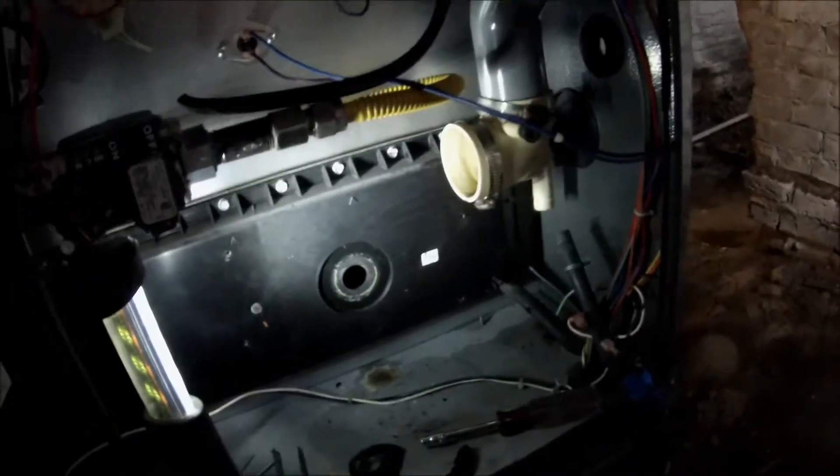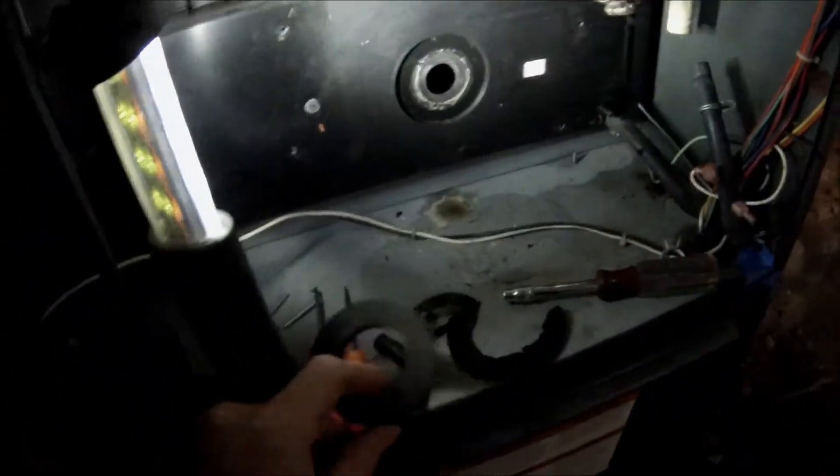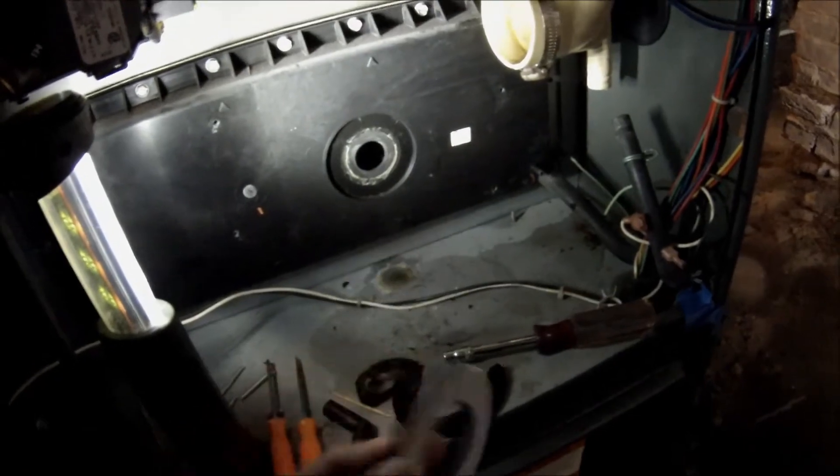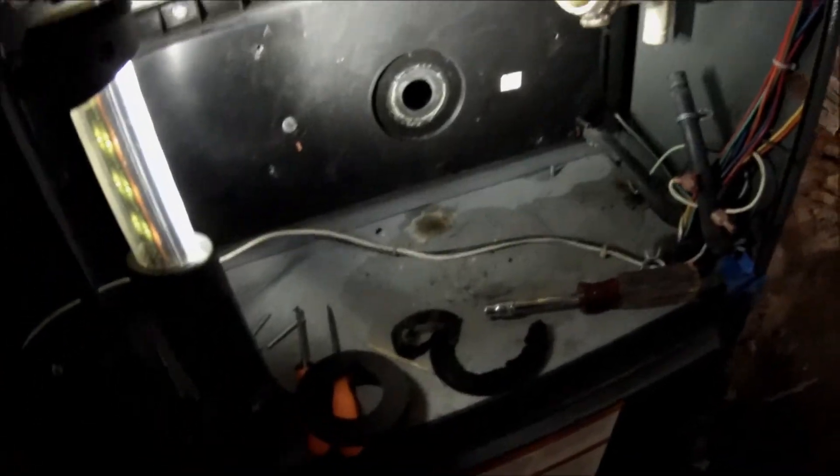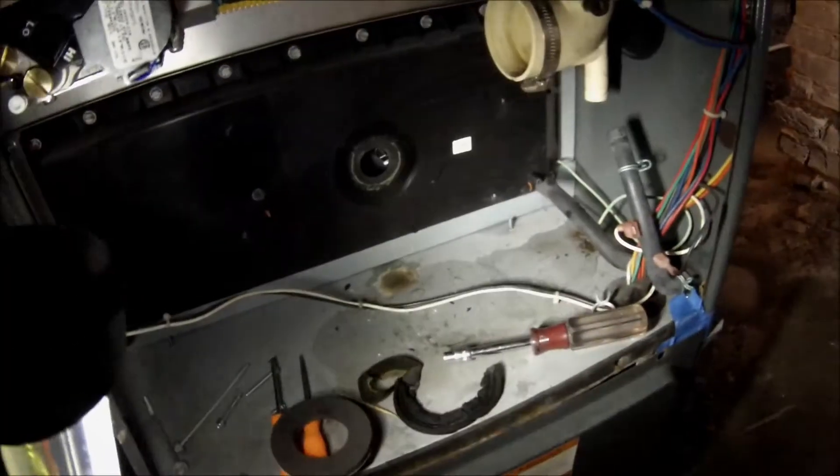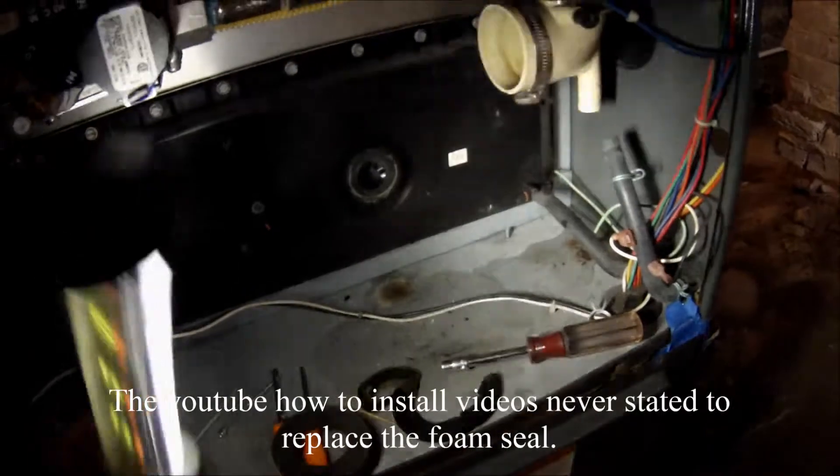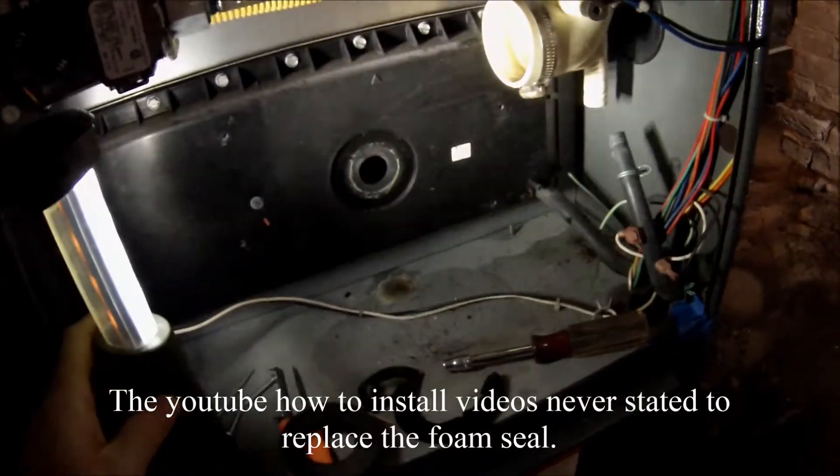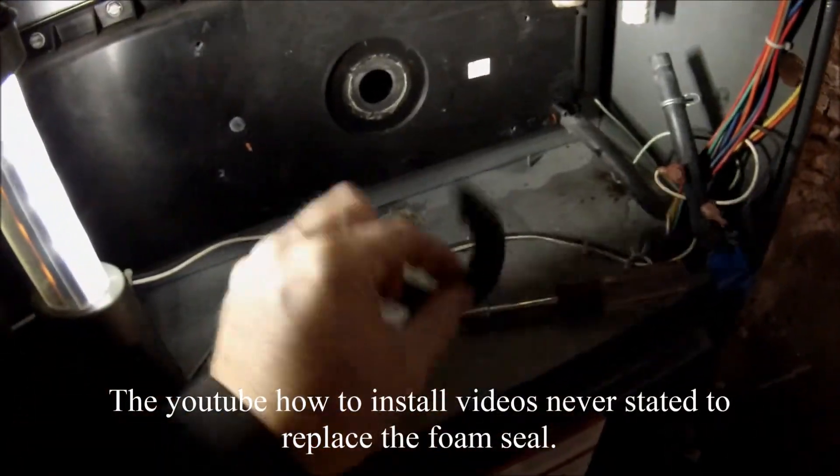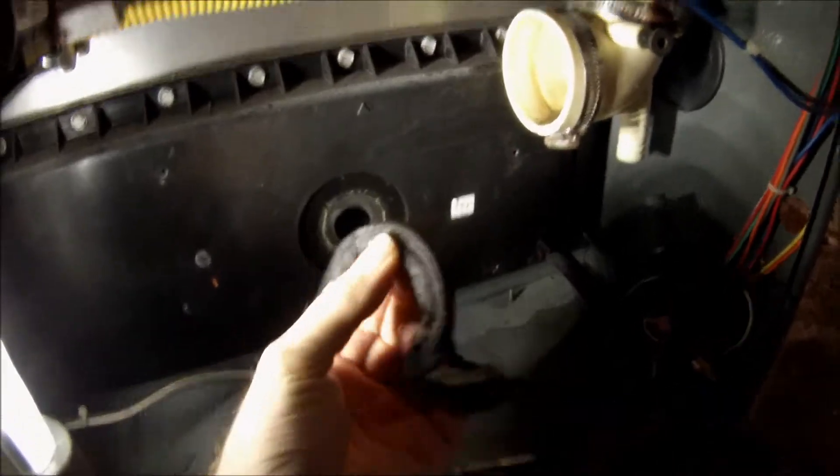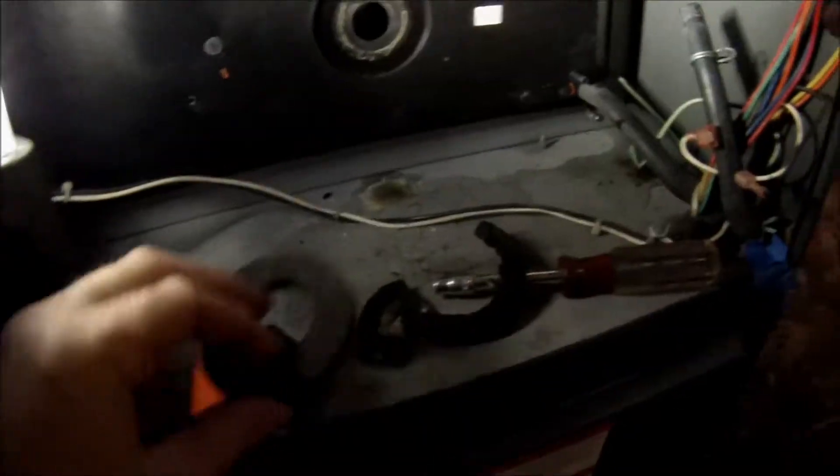So if you ever replace an inducer motor like this, and you might have the same problem as I did. It came with a new seal. And I figured I don't need it. Because the videos I watched of people that had these seals or replaced it, they never even mentioned replacing that seal. So if you look at my old seal here, see how bad that is compared to this new one.